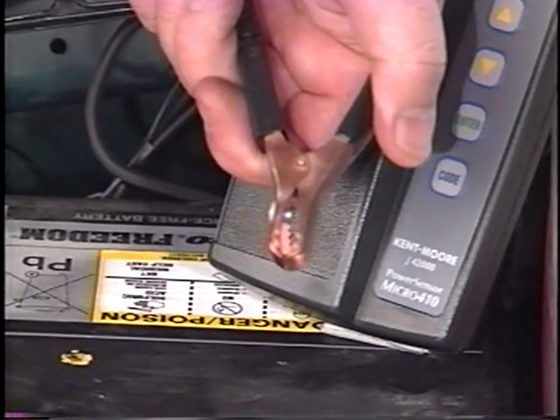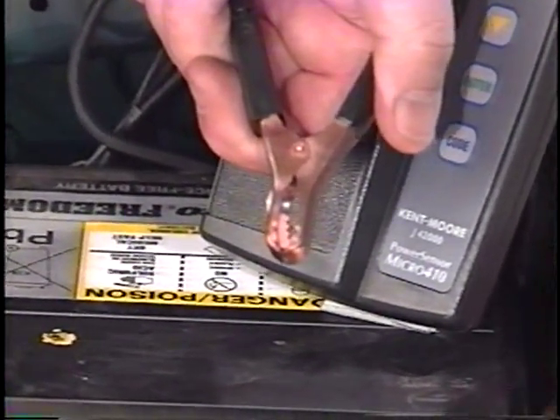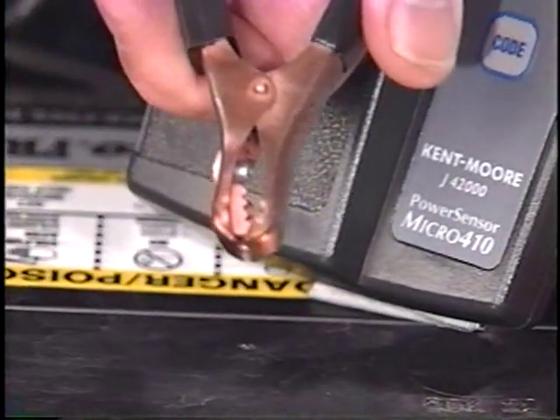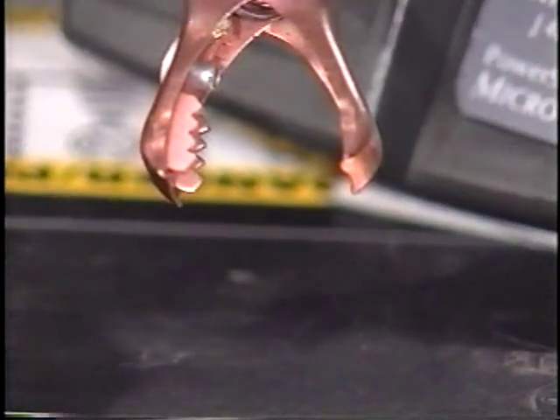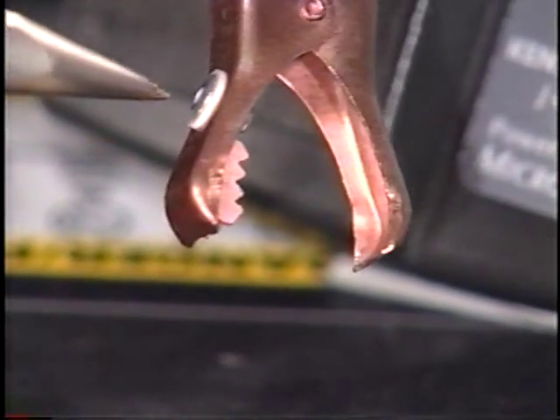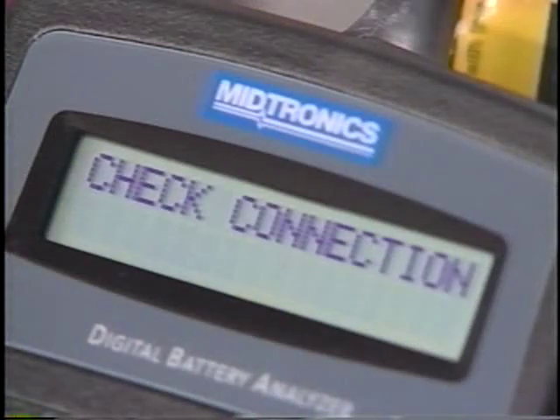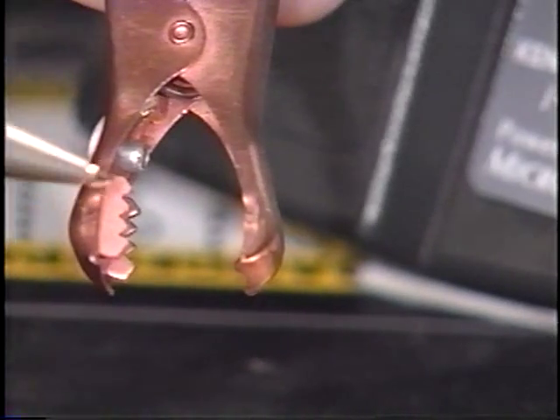The J42000 uses a special Kelvin connection to each battery terminal. That means we have both an AC and a DC terminal, accomplished through the serrated edge, which is insulated via a special washer from the body of this clamp. A poor connection message will be displayed on the screen if you don't have full contact on both terminals with both the serrated edge and the body of the clamp.